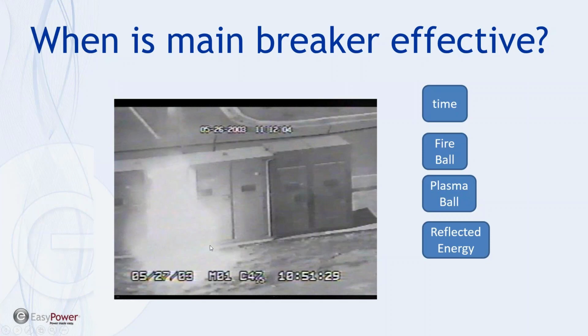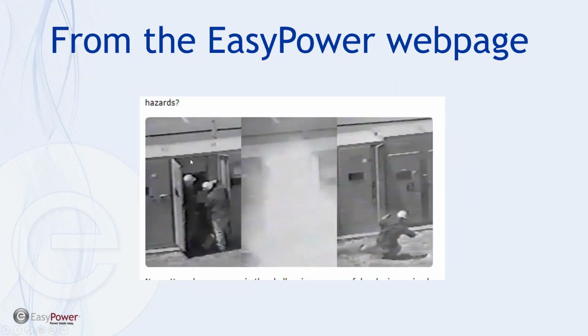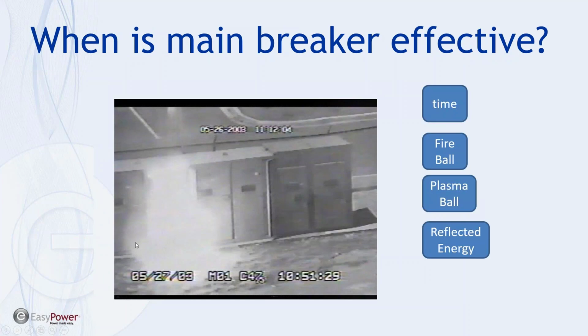So first of all, if you notice this kind of circular area at the bottom of the cabinet, let me go back. What we're talking about is a situation where 3 people were standing clearly within the arc flash boundary without adequate PPE, and we can see that this door is potentially closed to the back of one individual, and so the picture we're looking at is going to include the effects of that door shielding the radiation or the explosion. So again, the circular area is the fireball, and you can see quite easily it's probably 6 to 8 feet in diameter, and all 3 individuals standing inside these doors are engulfed in that fireball.